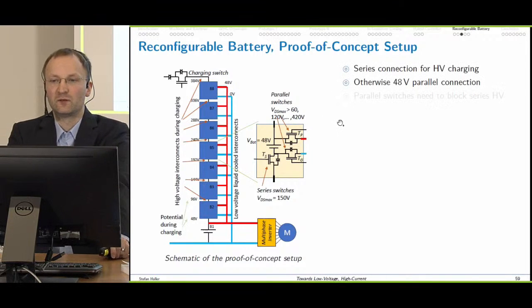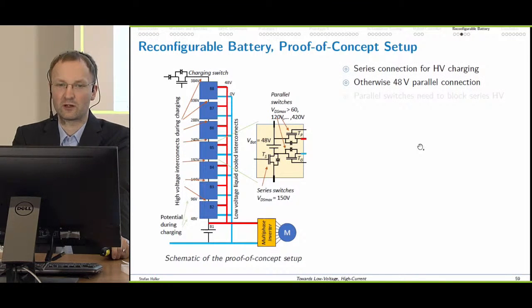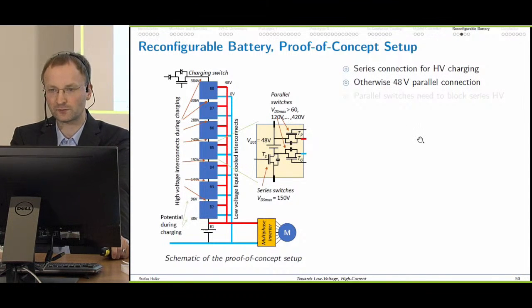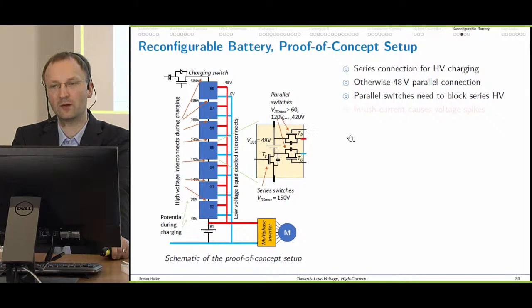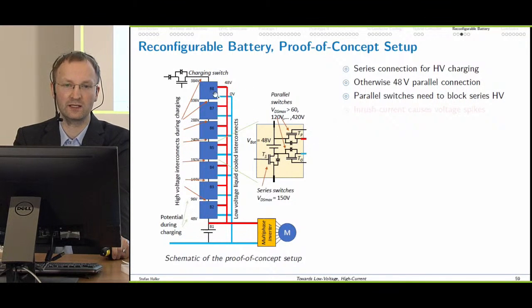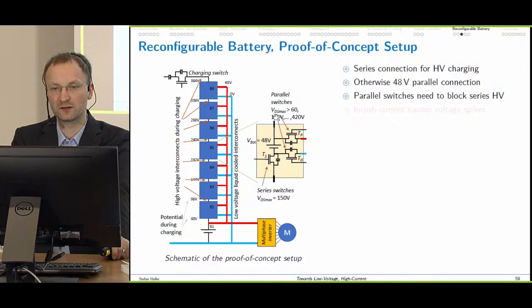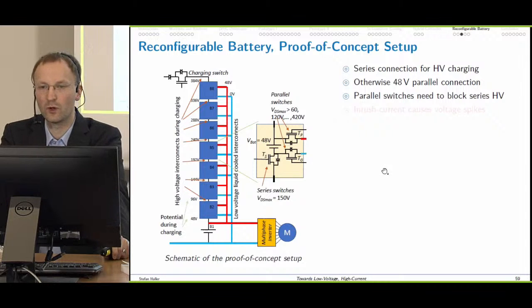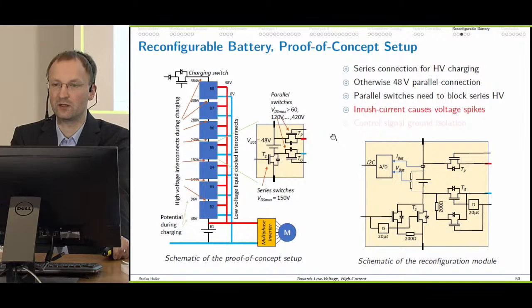So the battery is always kept in 48-volt parallel configuration, and only if we go for charging we switch it over to high voltage series mode. The observation here is that the parallel switches need to be able to block high voltage. The reason for that is if we now grab module number 8 here and assume 400 volt at this connection, and we have always 48 at the red link and always ground 0 volt at the blue link. That means we need to block at least 350 volt here at TP and at least 400 volt here at TG. What we also observed is that we have high inrush currents, creating high voltage spikes here.